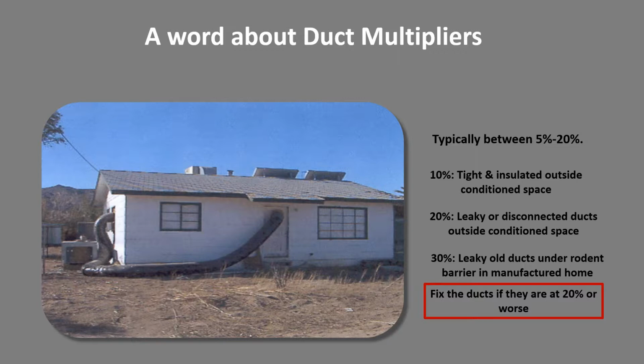Typically it's between 5 and 20%, and the duct multiplier is the penalty anytime you put the ductwork outside the house, either in the attic or the crawl space, sometimes the garage. 10% is about as good as you can get. That's well insulated and almost airtight. 20% is sort of normal. And if it's 30% or higher, you really should consider fixing the duct system. It's hard to make people comfortable with a bad duct system that delivers warmer air than expected in the summer and cooler air than expected in the winter.